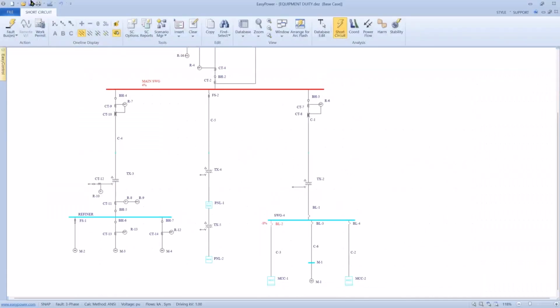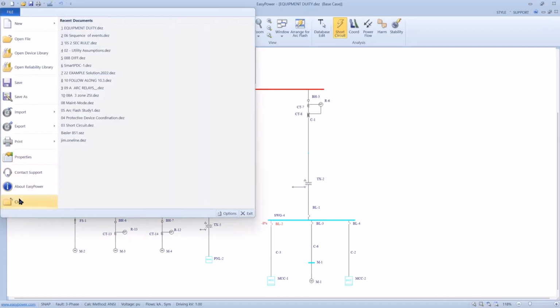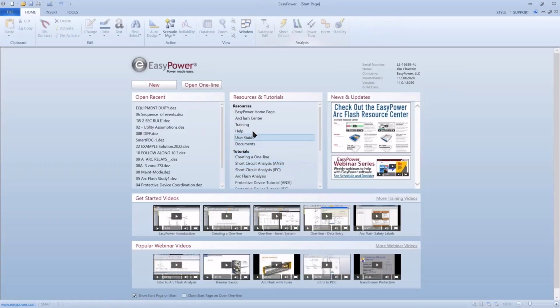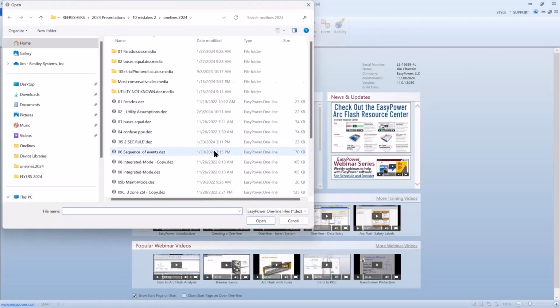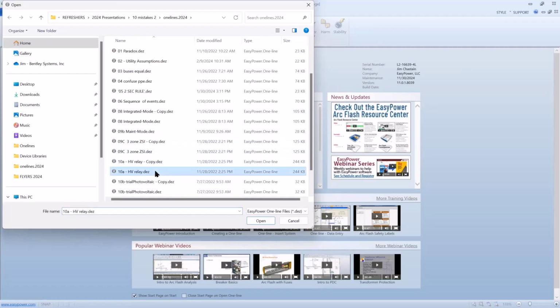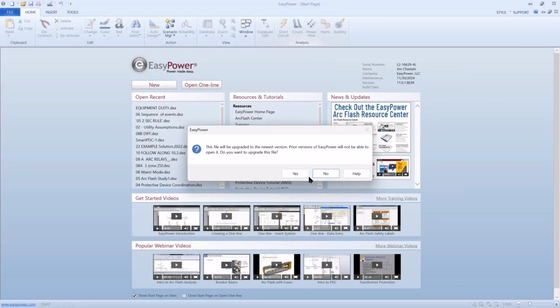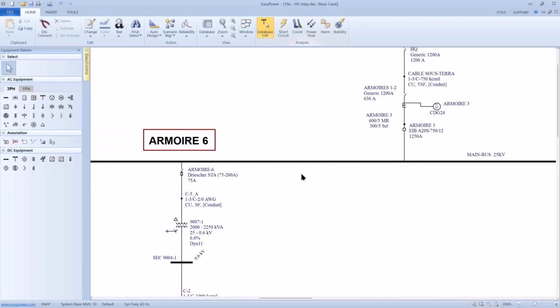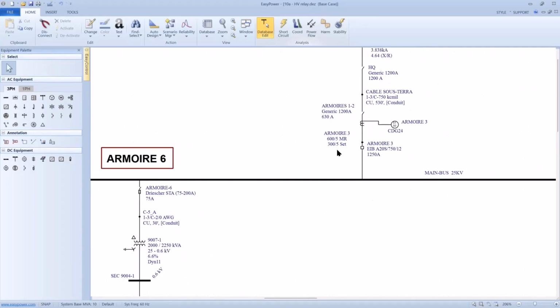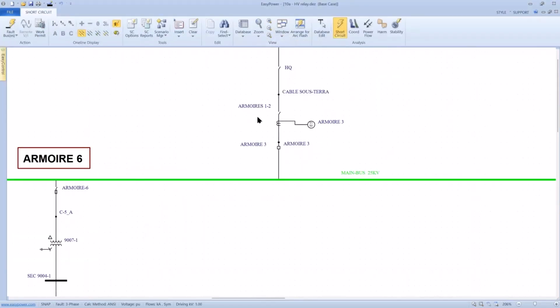This was a fun discussion because it took a bit for me to realize what was going on. And what made it even more fun, it was a real system, and we were looking at the trip session. Okay, so the question was: I know this is set for 1800 amps, and yet when I fault this bus, which has 4,000 amp fault current, it's not tripping the relay. And we're getting very high incident energy. He says, and when I make adjustments on the relay, it doesn't change this number.